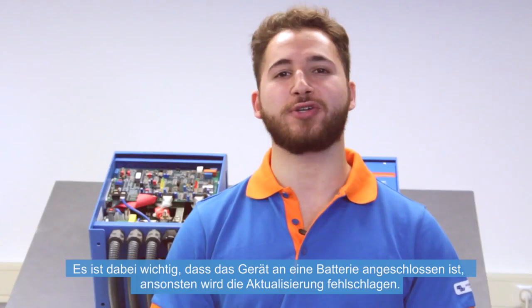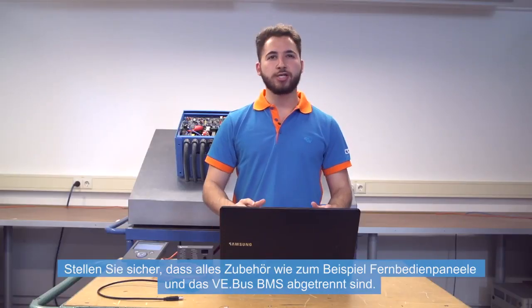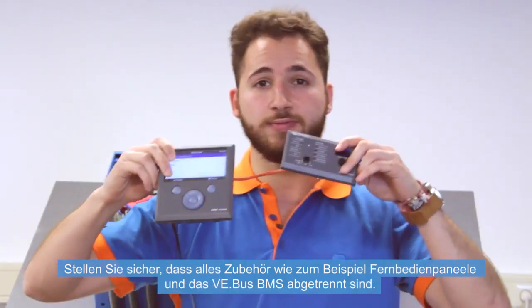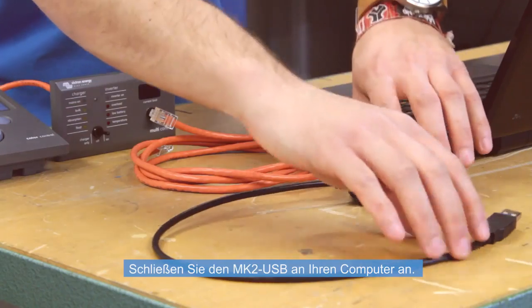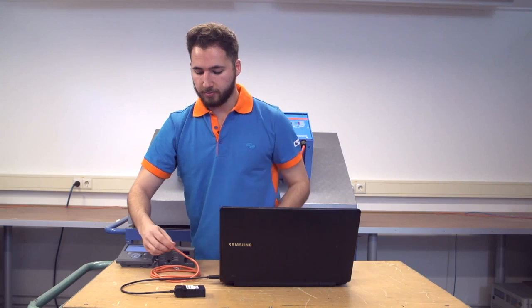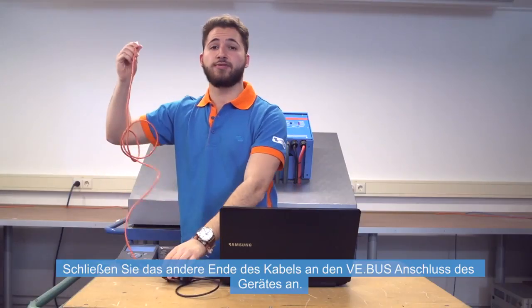It's important that your device is connected to a battery, otherwise the update will fail. Make sure to disconnect all accessories such as remote panels and the VE Bus BMS. Connect the MK2 USB to your computer. Connect the RJ45 UTP cable to the MK2, then connect the other end of the cable to the VE Bus port of the device.